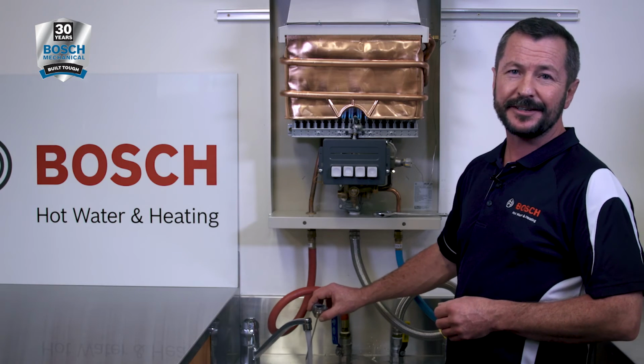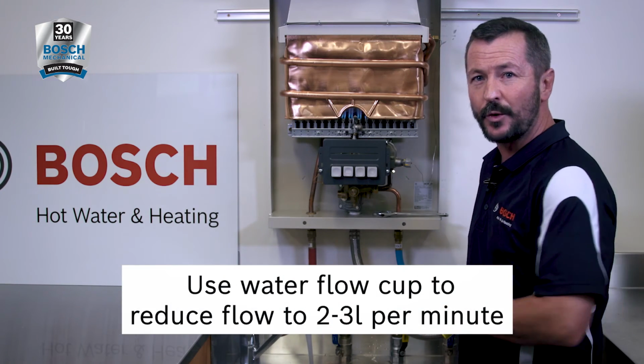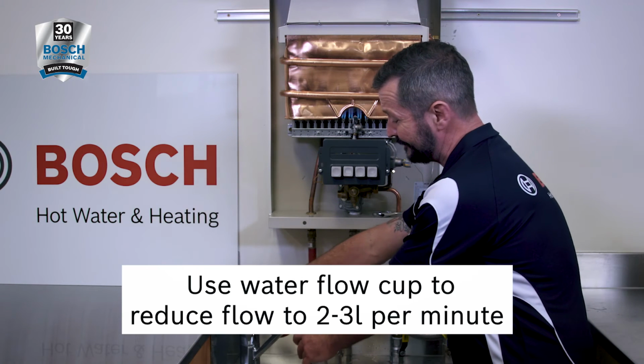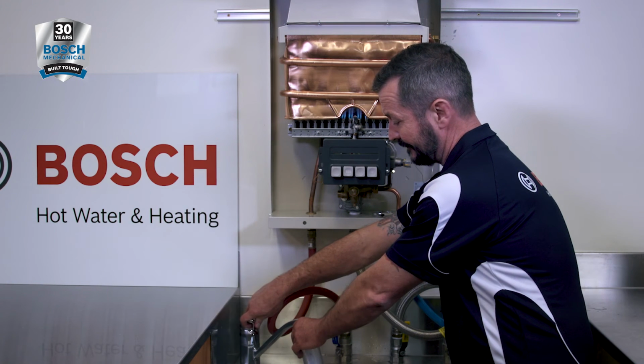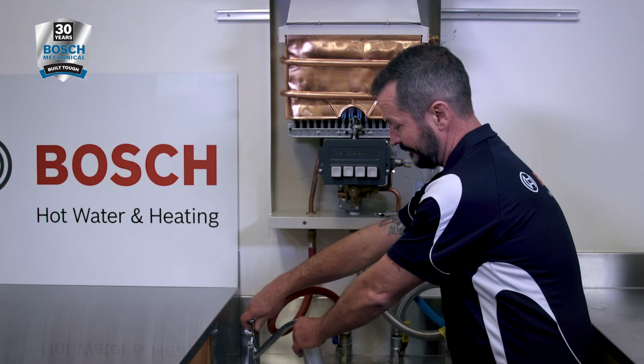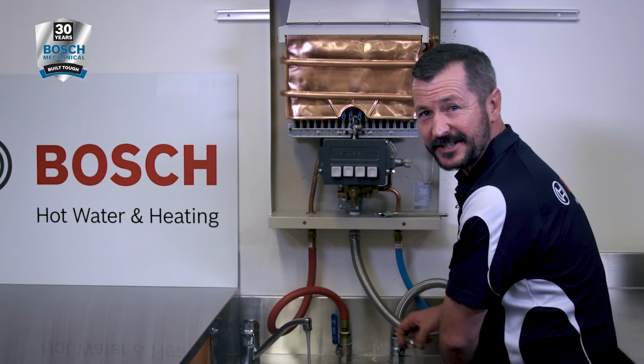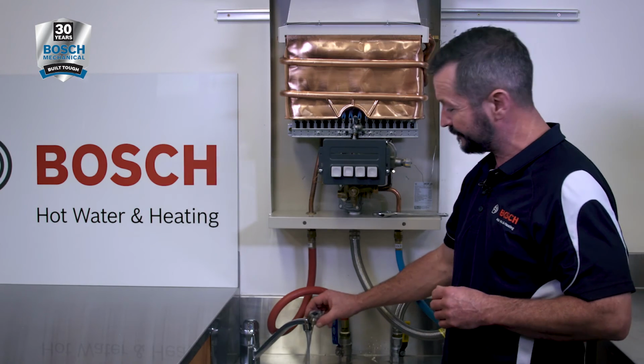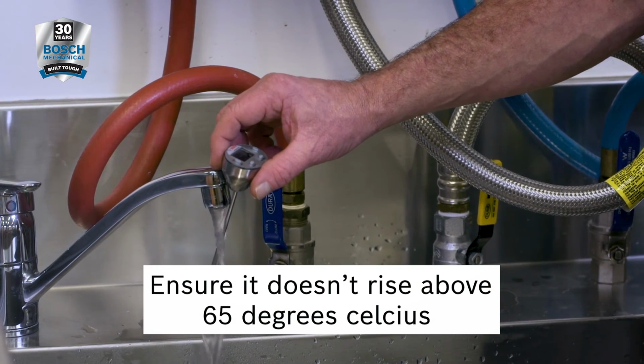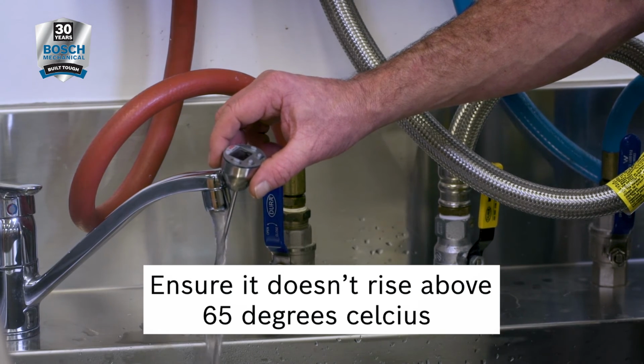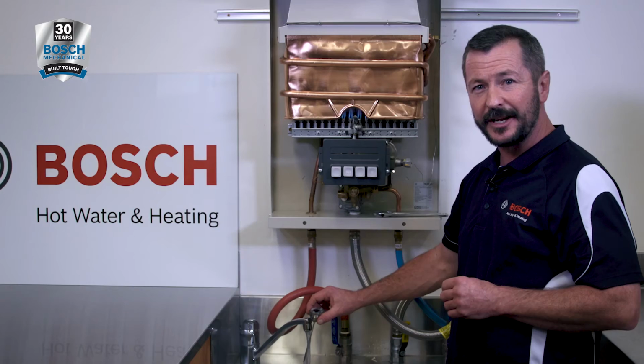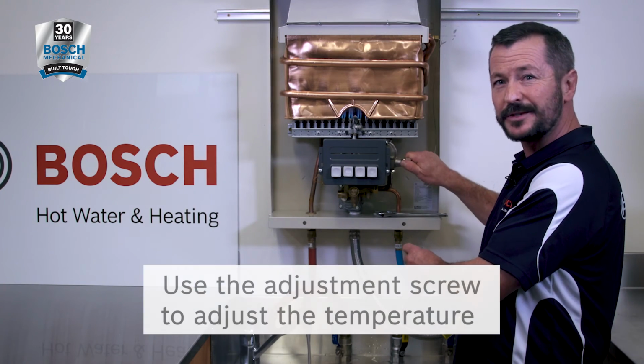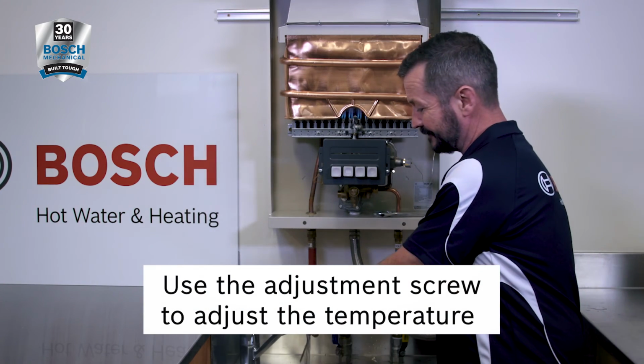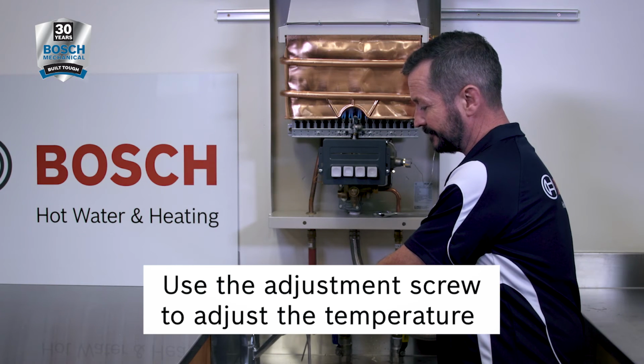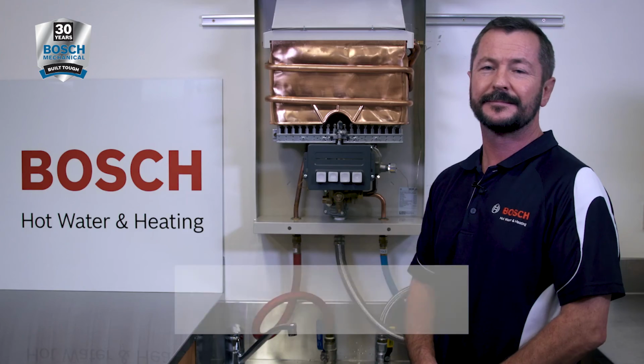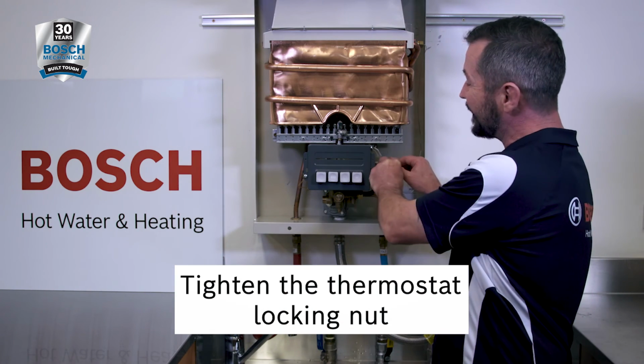Once we have the thermostat calibrated at 60 degrees, using your flow cup again, reduce the water flow down to about 2 to 3 litres a minute, and then check that it doesn't rise above 65 degrees with your thermometer. If it does rise slightly above 65, you may need to tweak it down towards the minus sign just a touch. Once the thermostat is calibrated, tighten the locking nut of the thermostat.